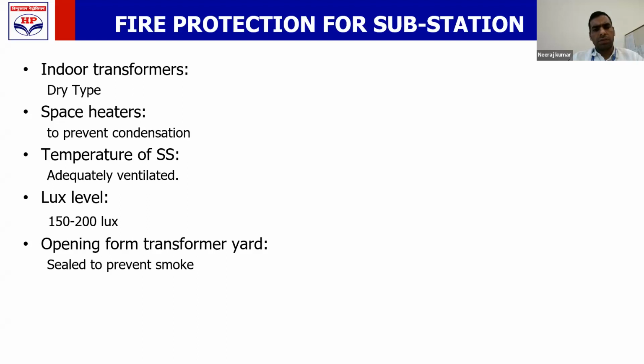How is it important to fire safety, fire hazard? If the ambient temperature inside the substation is higher than surrounding, then many of the specifications of the panels and other equipment, which say that this is designed for a particular temperature of say 40, may not be met. Your actual temperature may be 45 or 50. So you should ensure that your temperature inside the substation remains at ambient level or lesser than that. Plus lighting. The requirement for a substation is 150 to 200. That much lighting you should ensure inside the substation. 200 lux we'll try to maintain.